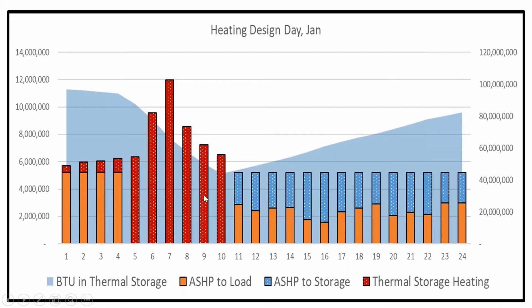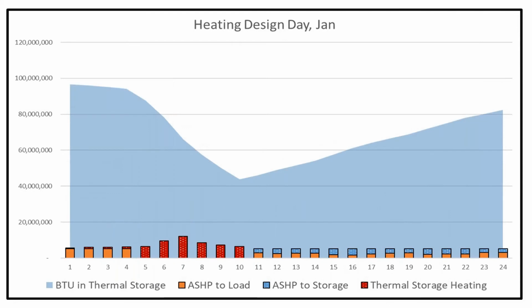And then when you get to the on-peak hours, and this on-peak hour is going to be a big deal for the utilities as we move towards electrification. It's peak hours now in the wintertime, but it's going to get much more intense as we add heat pumps. So in this particular case, we have turned off the air source heat pumps totally. So we've gone to full storage here. And now we're taking energy from the storage tanks and pumping it up to a usable level and meeting the load of the building. Now, a better way to see the graphics on just how much energy you have stored in these tanks. Now I only have one scale. I've got just the 100 million on the left. And so this is the same building load profile down here, but now I'm showing you how much energy is in storage.